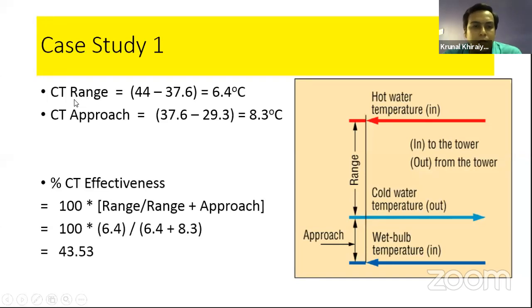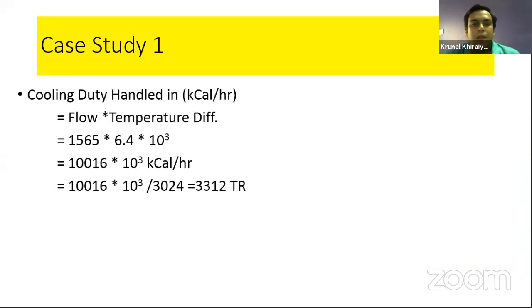And from the CT, meaning cooling tower range and approach, we calculate the effectiveness, and the effectiveness comes to about 43.53%. Then how are the TR utilized? That means, what is the installed capacity of the cooling tower and what exactly is the TR we are using. So the TR that we are utilizing: water flow rate is 1565 into the range, the temperature difference, into 10 to the power 3 to convert the meter cube into kilograms. And finally, for conversion of kilocalorie per hour to TR, we need to divide it by 3024. So finally we get 3312 TR, that we are currently delivering.